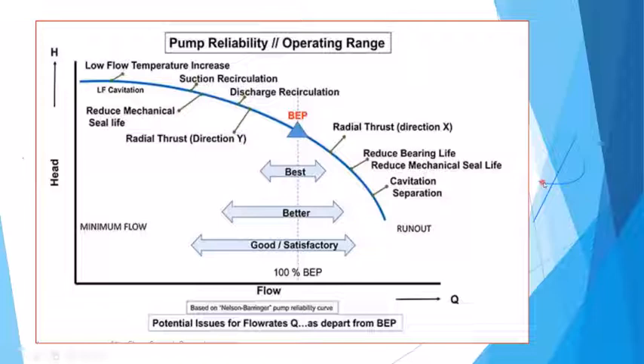That's what's most important, because when you get running these off the curve, because you're running a little bit too far off, they use a VFD to fix their problem, bringing it back in, but they forget about the losses that are in there.